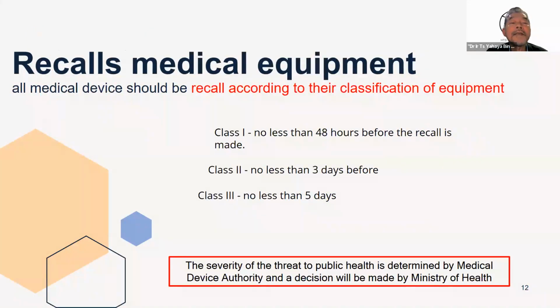Okay, in terms of recall of medical equipment, all medical devices should be recalled according to the classification of the equipment. So what are the Class 1? Class 1 is, again, as I said, high-risk equipment. There is a reasonable probability it will cause serious health consequences or even death. So it has to be reported within 48 hours before the recall is made.